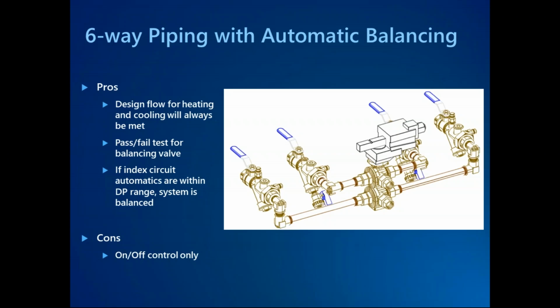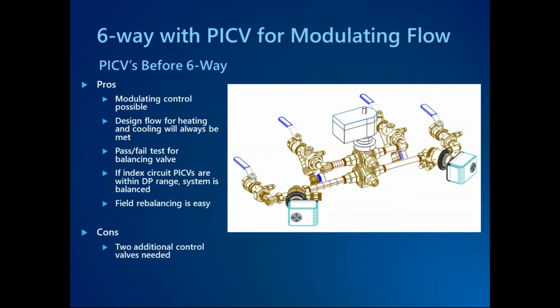A lot of times, this is the kit that might solve all the problems for tying that 4-pipe system into a 2-pipe chilled beam zone or a 2-pipe fan coil, whatever it might be. But I want to look at some other things that you might see in the marketplace, if not today, then coming down the pike as kits out there that we're starting to see. First one is going to be tying PICVs into the 6-way kit. The 6-way itself is going to purely act as the on-off changeover device, while the PICVs are going to be providing all of the modulating flow control.